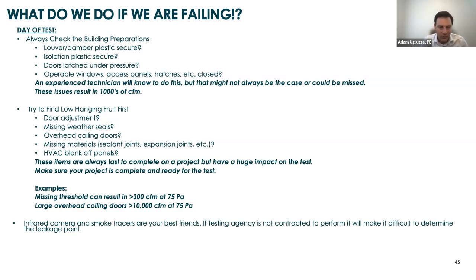As I mentioned, coiling doors, same thing. I mean, thousands of CFM. Some of the bigger doors just can't seal. They bend in the middle because they're so big. So there's only a limited amount that you can do to make sure that you're passing. And then lastly, infrared camera and smoke tracers, they're your best friends when things aren't passing. That's the equipment that you're going to use to figure out what the heck is going on.